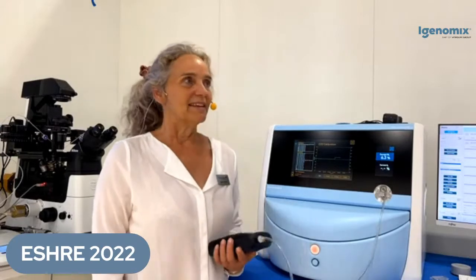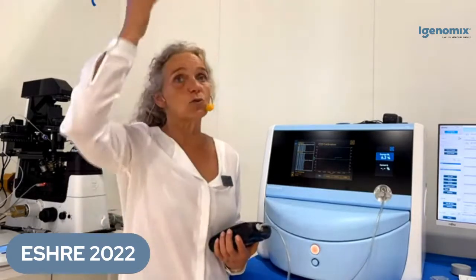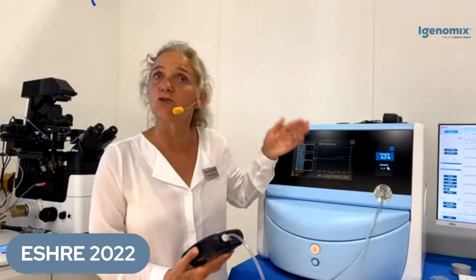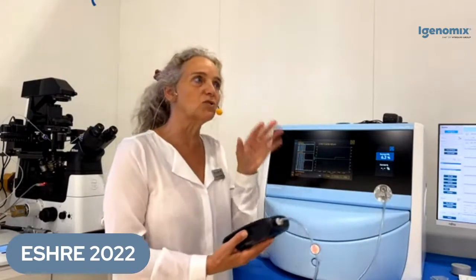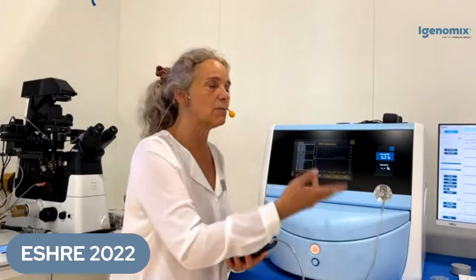What I would say of when you should actually calibrate: we don't recommend you to calibrate when the deviation is 0.2 and less, because weather-related changes, when there is a storm or low and high pressure, affect your analyzer. The EmbryoScope by itself will take that into account, so you should not be afraid of that. But when you do your analysis, you'll get a wrong reading. So don't do your measurement and calibration if it deviates less than and up to 0.2.